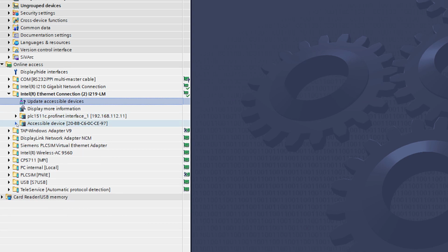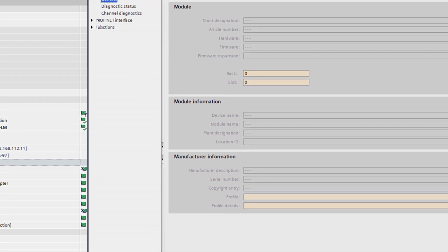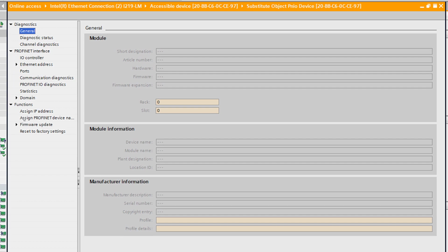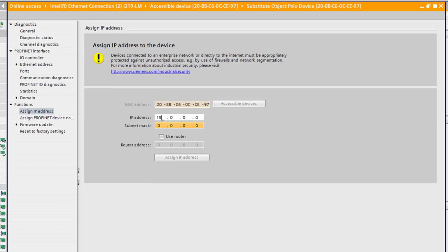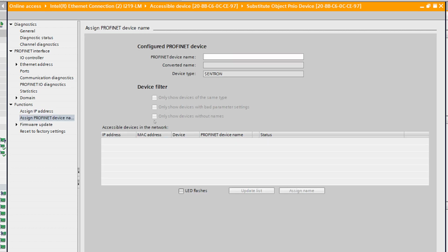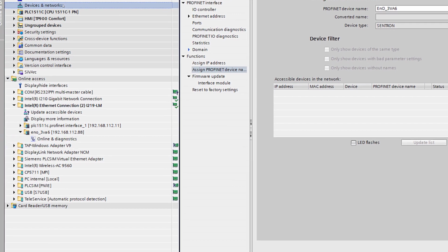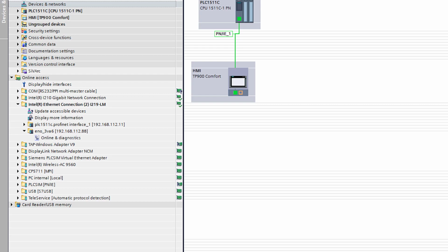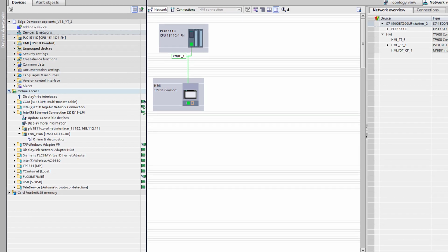Right now, we'll treat the device that we just installed the expansion port on as if it were new and unprogrammed. Here you can see through the accessible devices in the online and diagnostics that we can come to the functions and assign things like IP address and Profinet device name for the very first time. Once the parameters are configured, just hit Assign IP. Next, moving to the Profinet device name, here with a meaningful name if we can. And then you can see correctly displayed here by name and IP address.